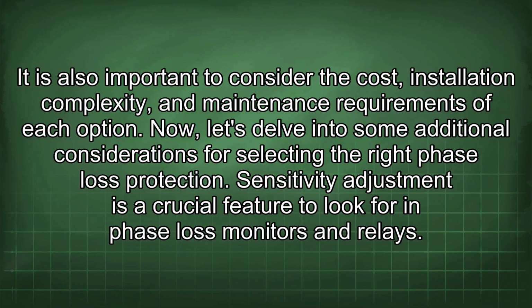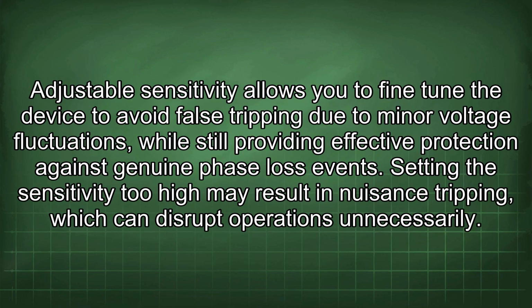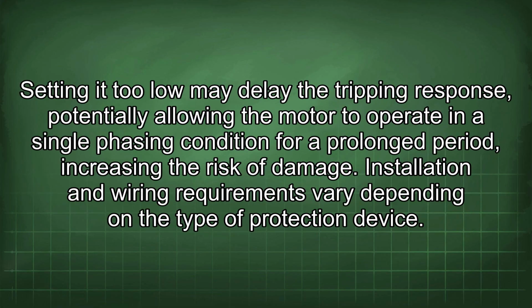Sensitivity adjustment is a crucial feature to look for in phase loss monitors and relays. Adjustable sensitivity allows you to fine-tune the device to avoid false tripping due to minor voltage fluctuations, while still providing effective protection against genuine phase loss events. Setting the sensitivity too high may result in nuisance tripping, which can disrupt operations unnecessarily. Setting it too low may delay the tripping response, potentially allowing the motor to operate in a single phasing condition for a prolonged period, increasing the risk of damage.